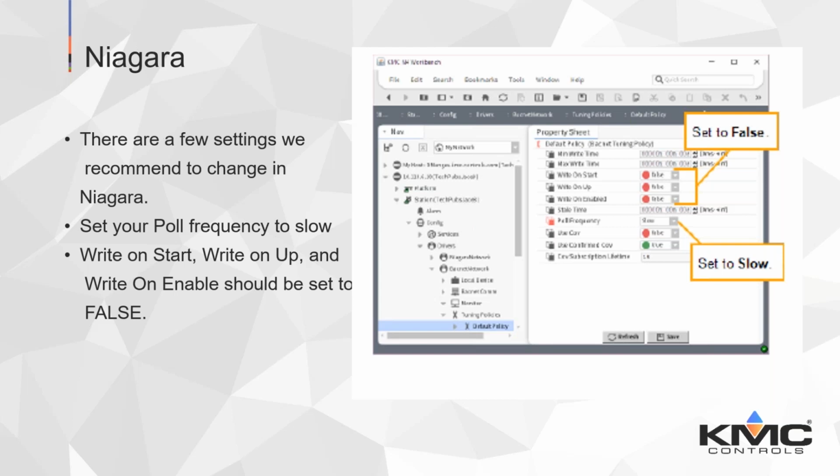So you're saying in that instance, we're going Niagara to the BACnet IP controller that is going to respond very quickly. Yep. And then this control basic code there would read and write from the translator at a frequency that the KMD network can absorb. Yes. So that gives us a little extra buffer and lets us control that request messaging a little bit better than just having Niagara do it on its own. It's going to be a lot harder to bombard that network at that speed, passing points back and forth. Great.